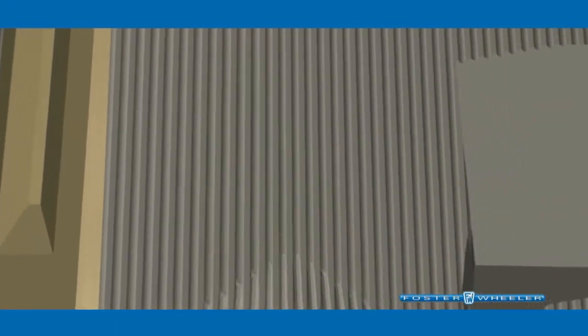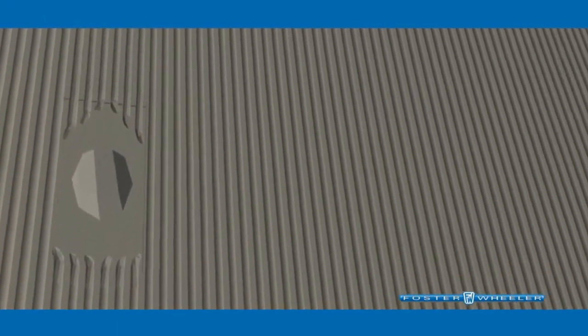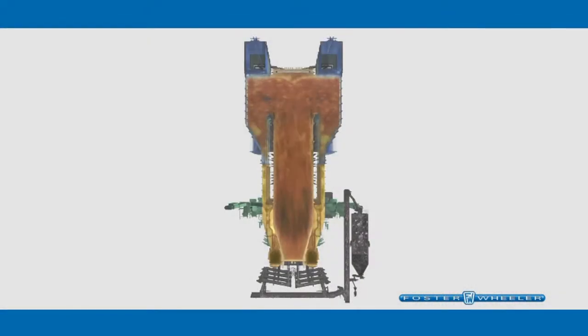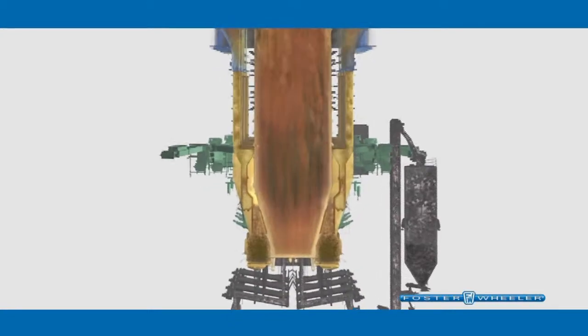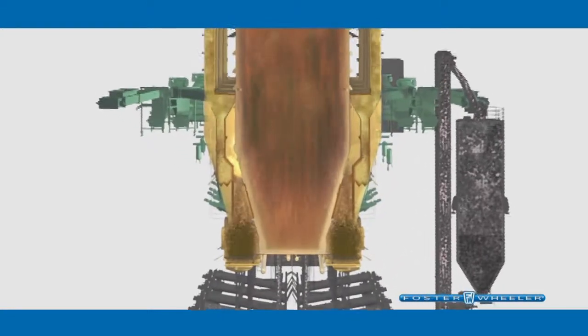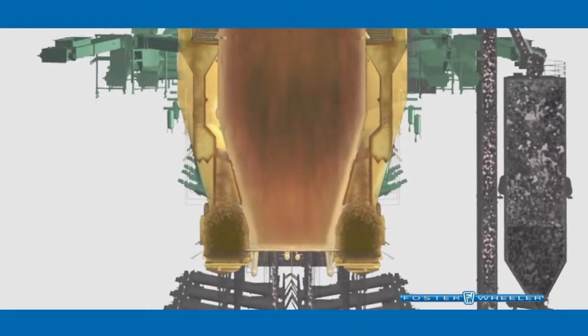Additional secondary combustion air is fed through ports located higher up in the furnace. The way this air is introduced into the CFB results in vigorous mixing of the solid fuel, limestone, and ash particles, allowing the CFB to cleanly burn almost any combustible material.